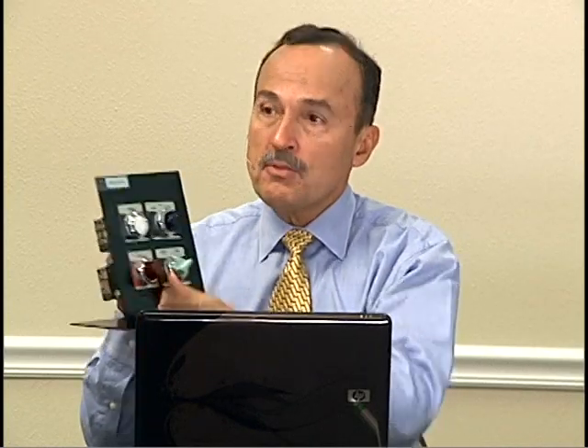Through your float switch. Or float switches, temperature switches, I'm sorry, whatever. I'm going to whatever your control devices I determine it to be. So I could go to auto, but the motor might not start if it's a 3-wire control circuit, which would require me then to go to the start button. And once I start it, it would run fine. But as soon as I lose power or I stop it, even in the auto mode, it's not going to automatically restart because it's a safety application or whatever the other conditions were.